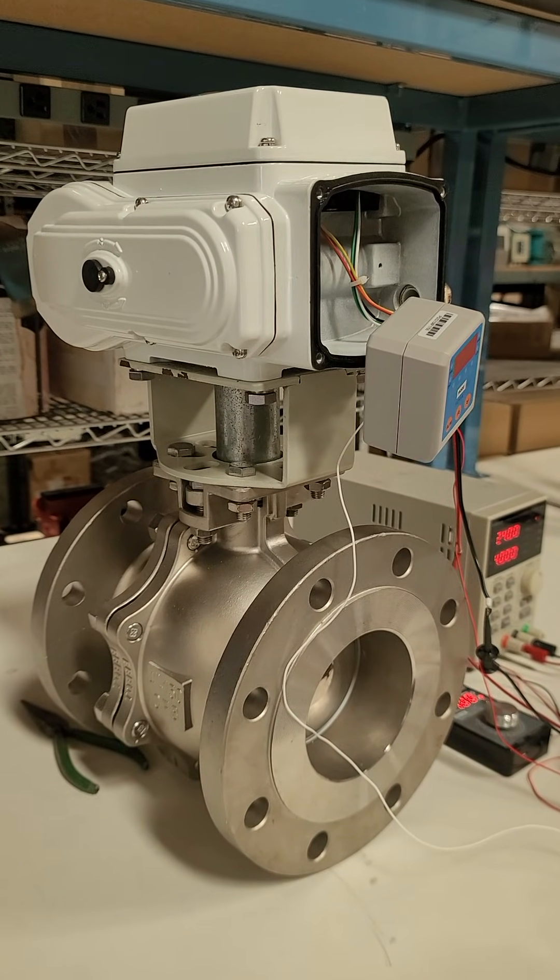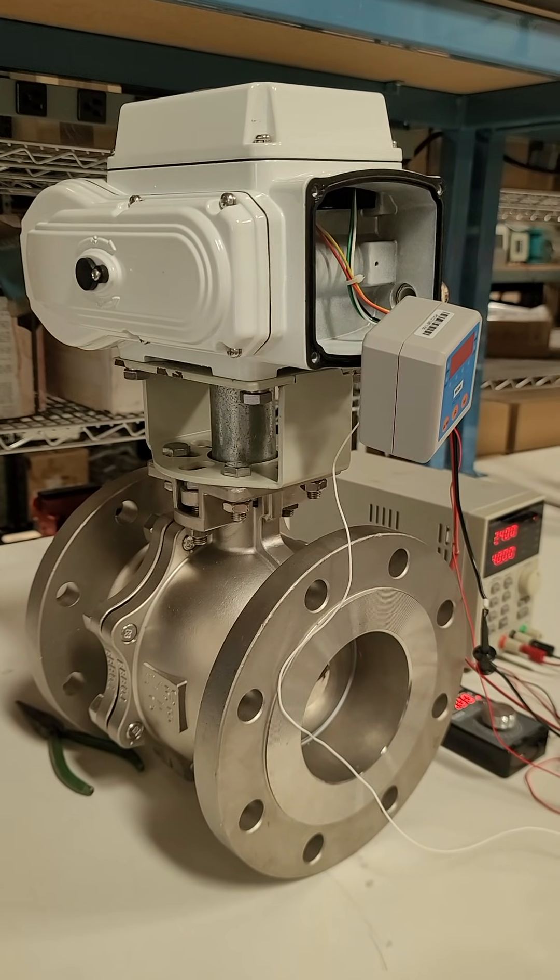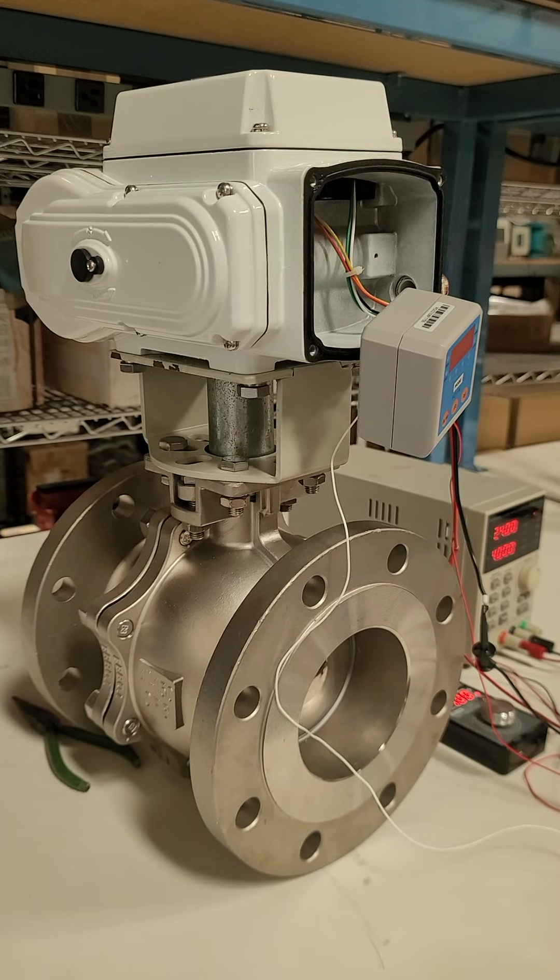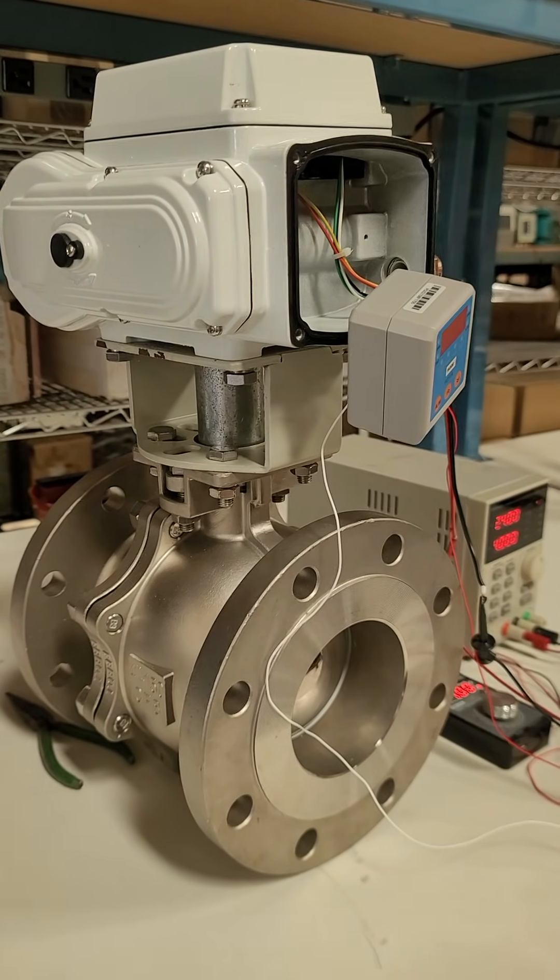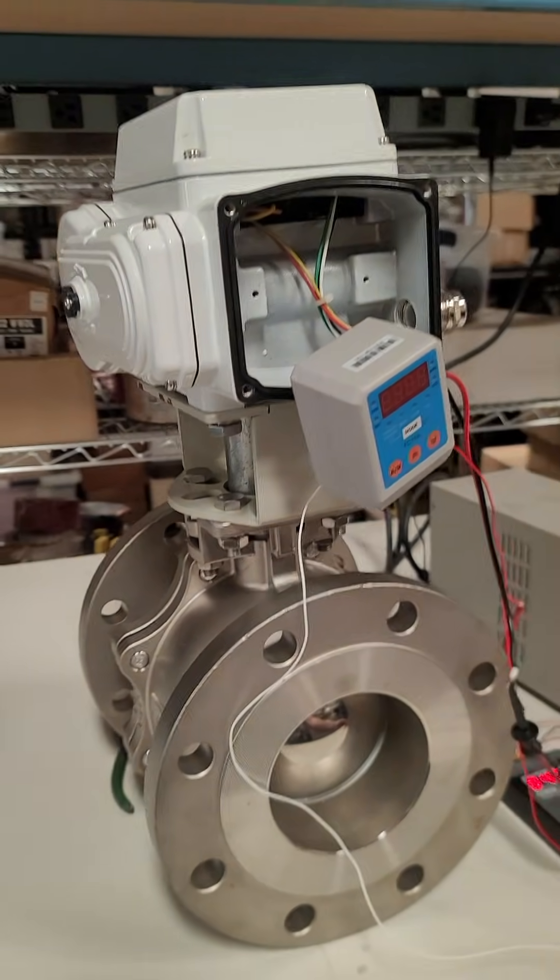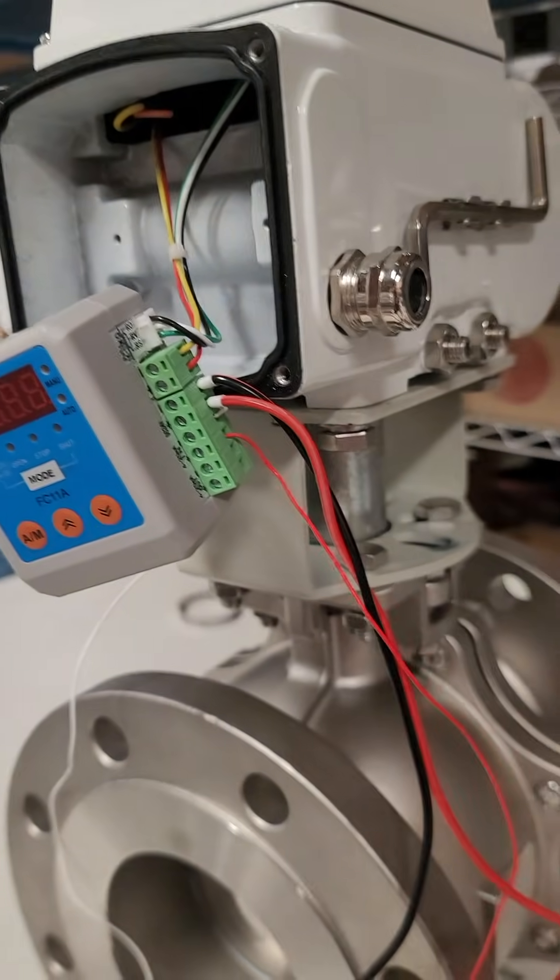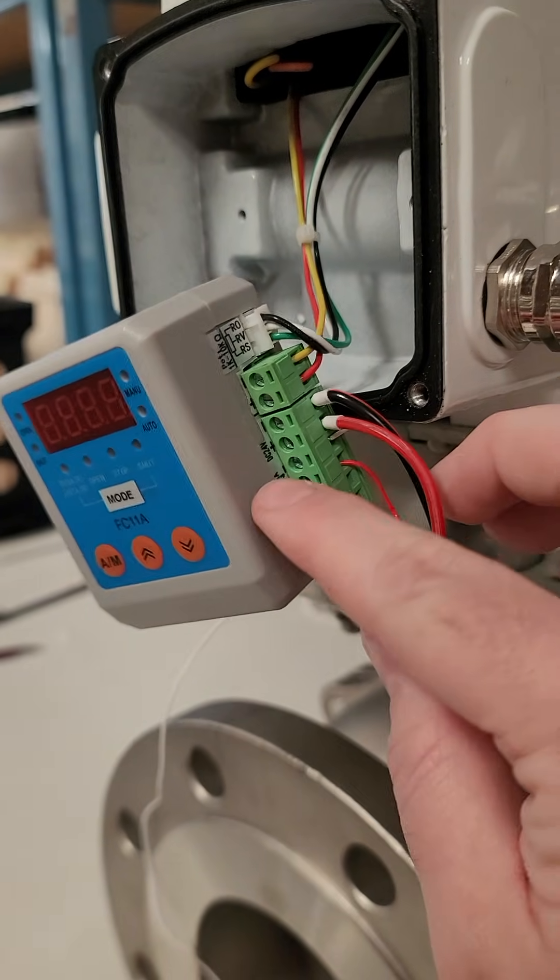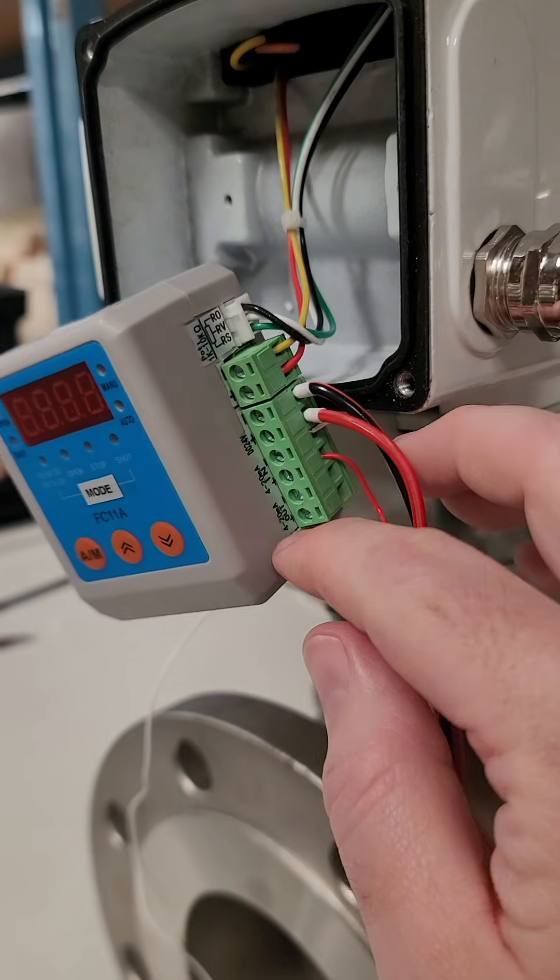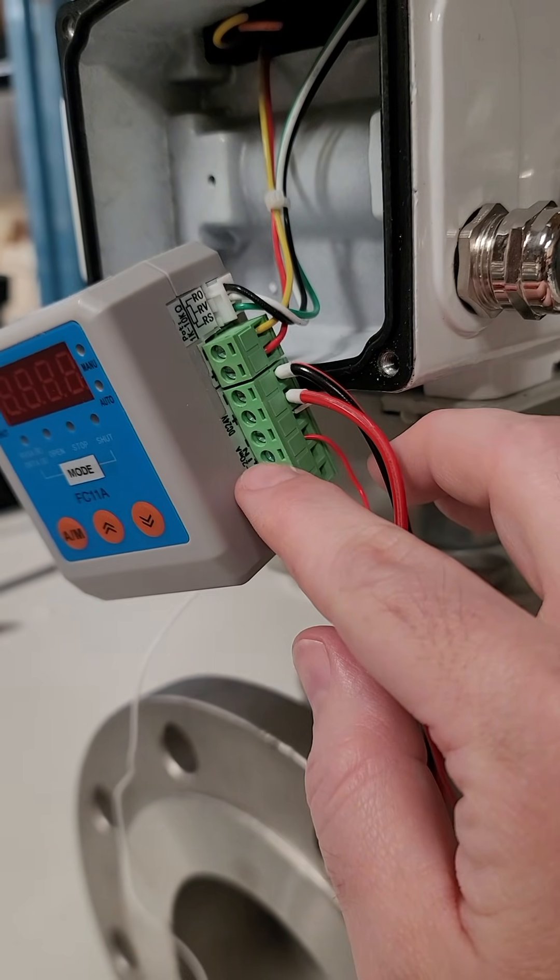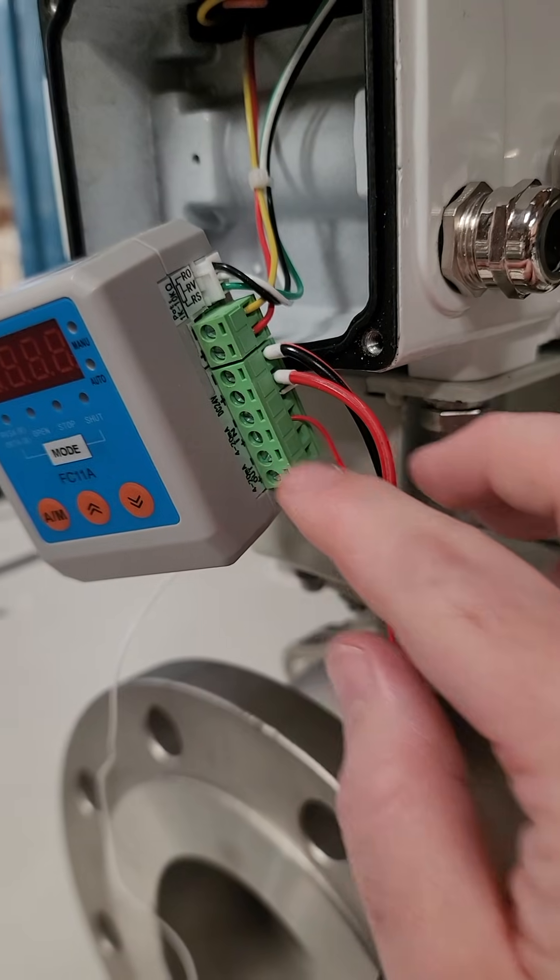Today I'm going to go over how to control these modulating control valves. This is a 4 to 20 milliamp input control valve system. We have our power supply hooked up to the 24 volts positive and negative, and then this is a 4 to 20 milliamp positive and negative.